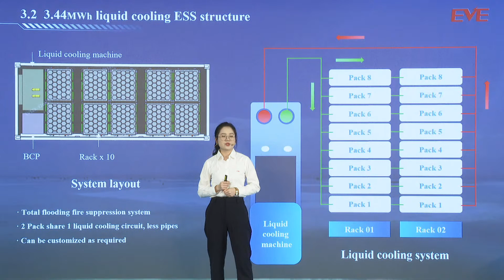The entire 3.44 megawatt-hour liquid cooling system is designed with 8 packs connected in series to be a battery rack, and a total of 10 battery racks. It has a 3-level BMS architecture. The BMS communicates with the liquid cooling machine and the battery through CAN protocol, and mainly communicates with the PCS through RS485, which is matched according to the PCS protocol. And the protocol between PCS and the EMS is Ethernet.